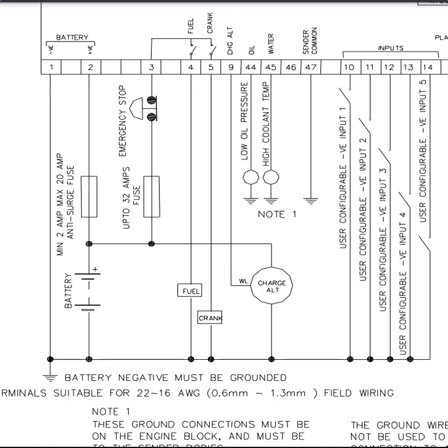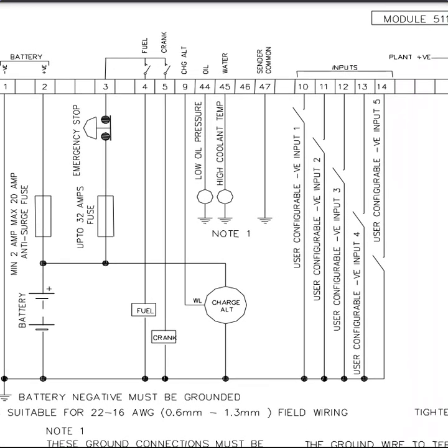Number 9, charging alt, that's the D+ wire. Oil pressure sender: you're literally getting a wire from the oil pressure sender and running it up to here. Water coolant temp, same thing. Get the wire from the water coolant temp and put it on 45. Then there's a sender common wire, which is going to be like a specific ground to the engine block. They don't want it hooked up to a ground bar with multiple grounds on there. It has to be an isolated ground.